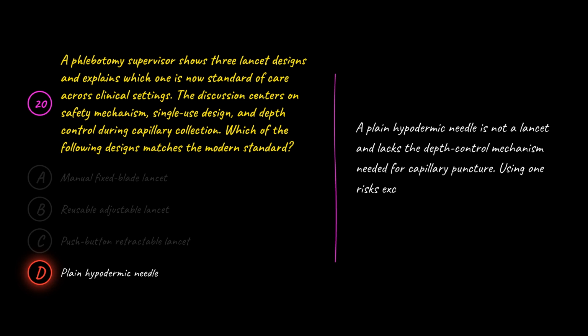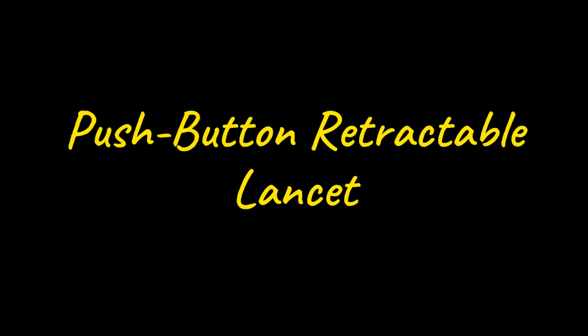Using one risks excessive depth and tissue injury rather than a controlled superficial cut. The push-button retractable lancet is the modern clinical standard for capillary puncture, replacing older manual fixed blade designs that left operators exposed to sharps hazards after use. Understanding why this device exists starts with the 3 problems it was engineered to solve.